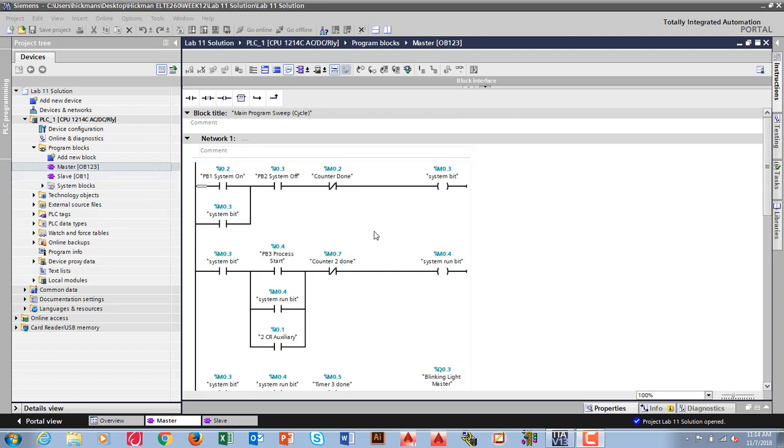So the first thing that you needed to do was make the connections. The master PLC had to have I/O wired into it, but it had to have control relay 1. The master must turn on control relay 1. The control relay 1 contacts must be wired into the second controller that I've called slave here. And now the slave controller must have control relay 2, so the slave controller has to turn on a relay, and the contacts from that control relay 2 must be wired as an input into the master. So that's how they're talking.